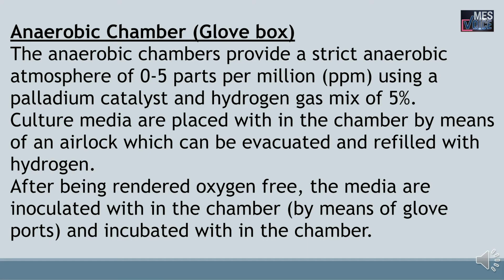Next is about the anaerobic chamber, also known as the glove box. The anaerobic chambers provide a strict anaerobic atmosphere of 0 to 5 parts per million using a palladium catalyst and a hydrogen gas mix of 5%.